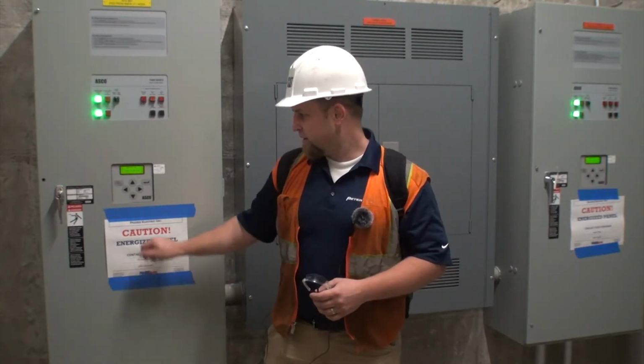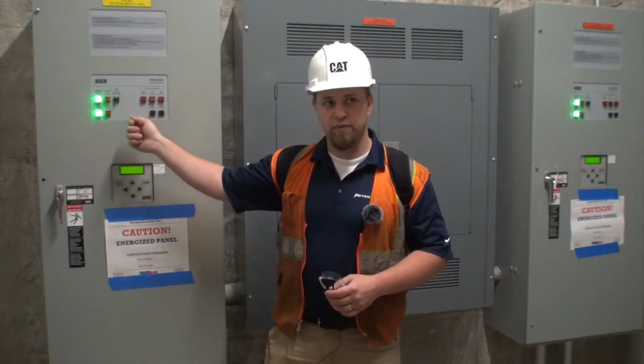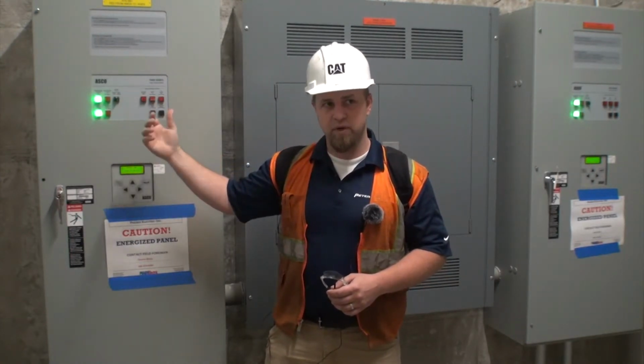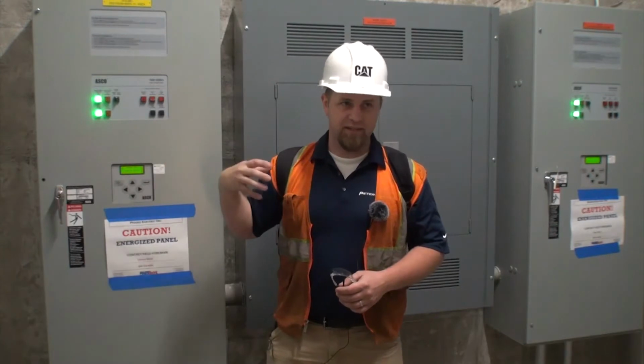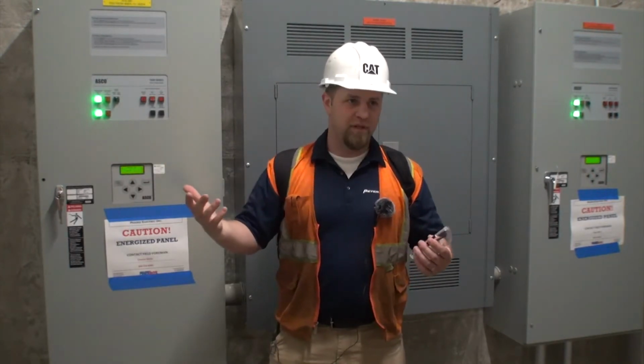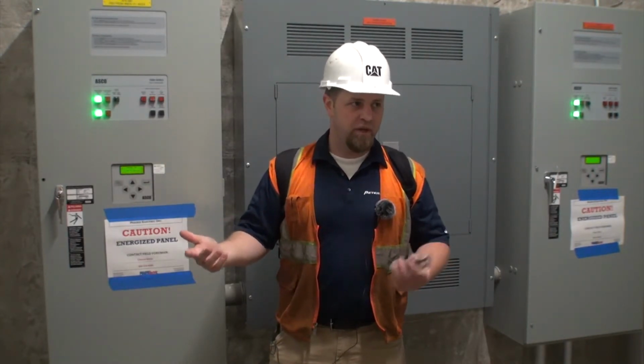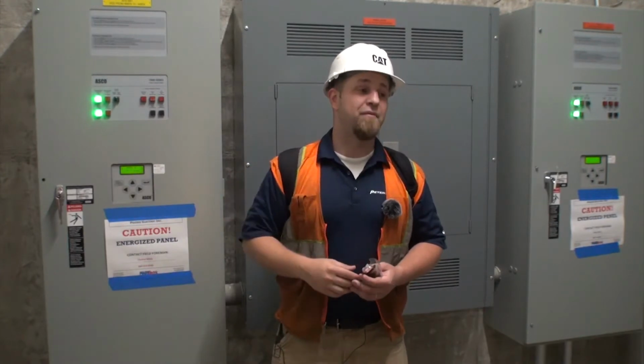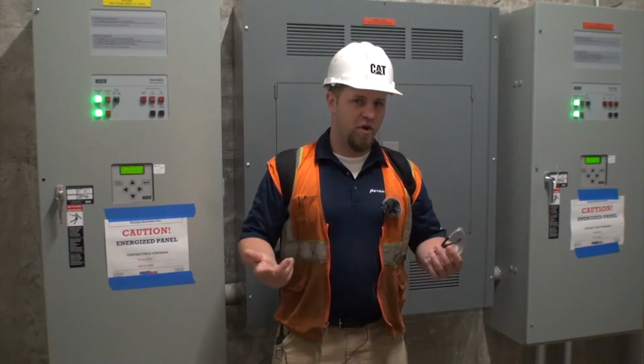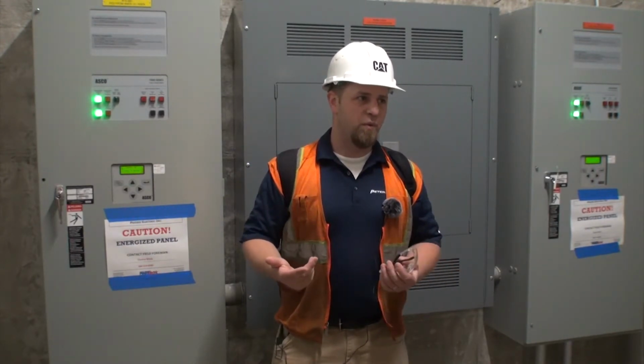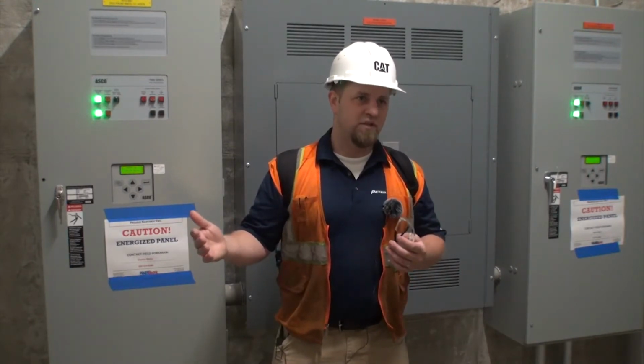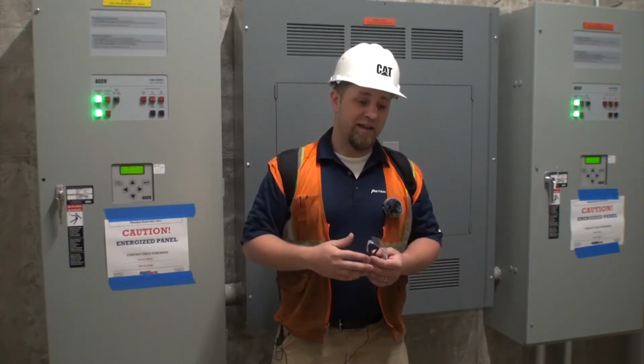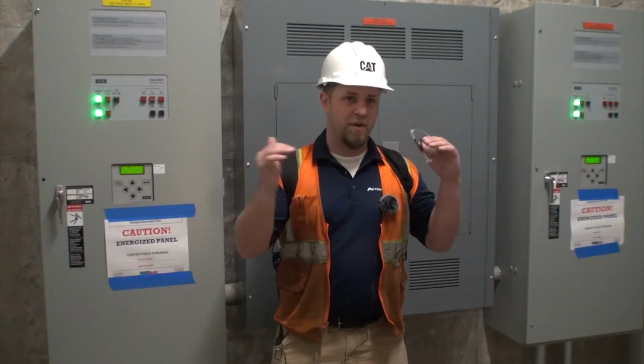Then come down here, do your transfer, hold for 15 seconds. It's going to transfer, run for whatever time delay they set it up for, 30 minutes is what the code says it needs to be. Then it's going to go back over, it's going to have a 5-minute cooldown. So don't be worried if it doesn't shut down right away, because it is going to have 5 minutes to cool back down. And like I said, it's also going to want to make sure it sees the right parameters.